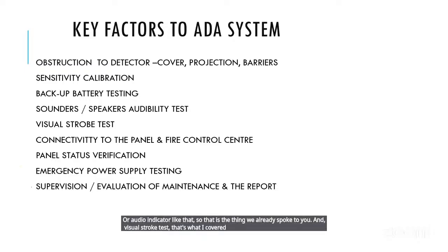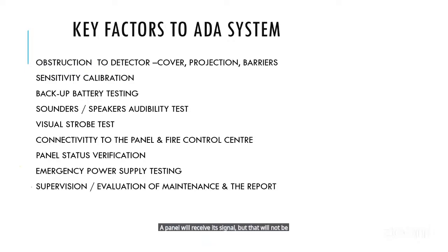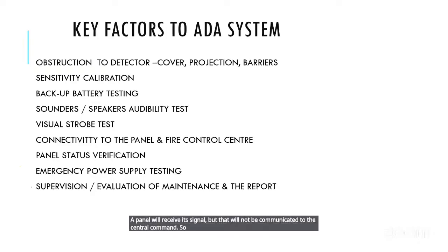And connectivity to the panel and fire control center is a very important thing. The detector will activate, but the panel may not receive its signal. The panel may receive its signal, but it may not be communicated to the central command. So the connectivity should be end to end. So that must be connected.